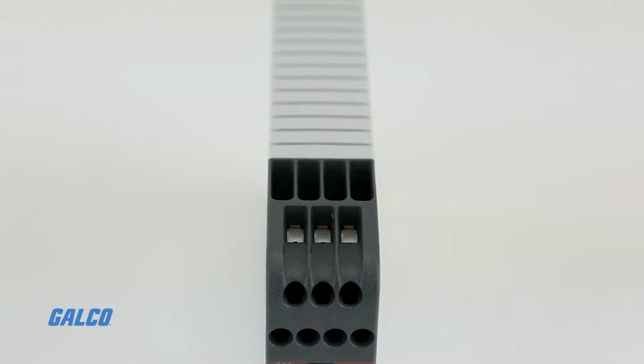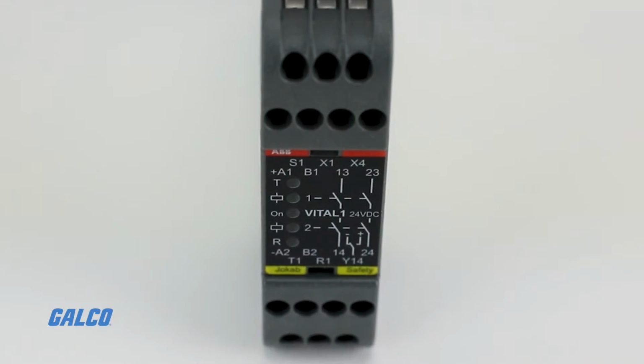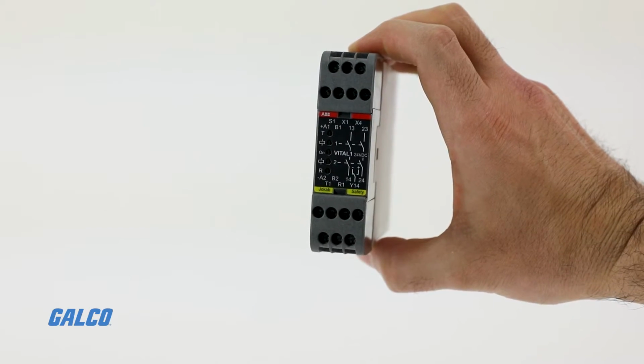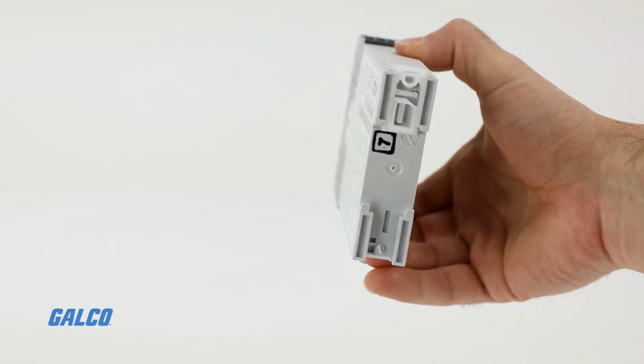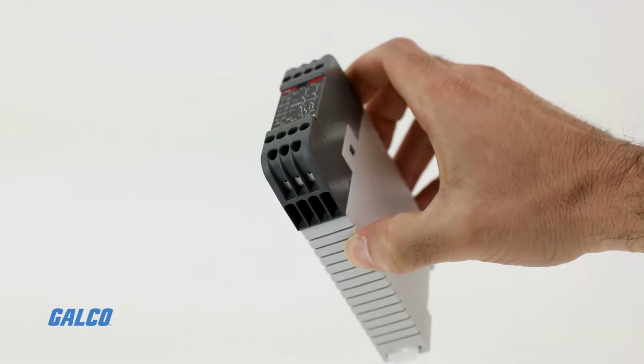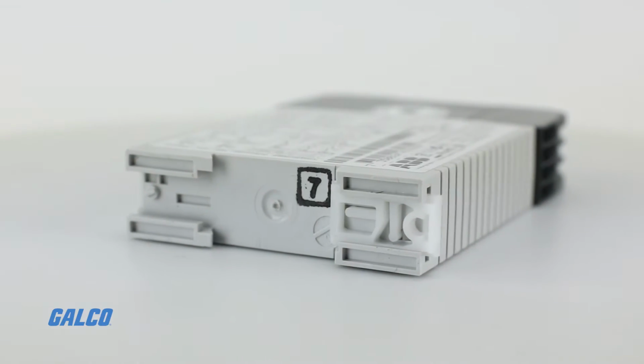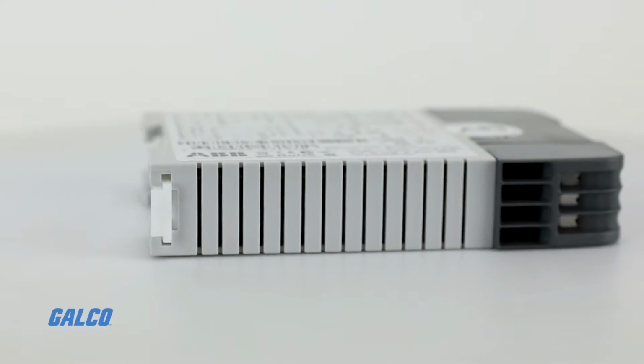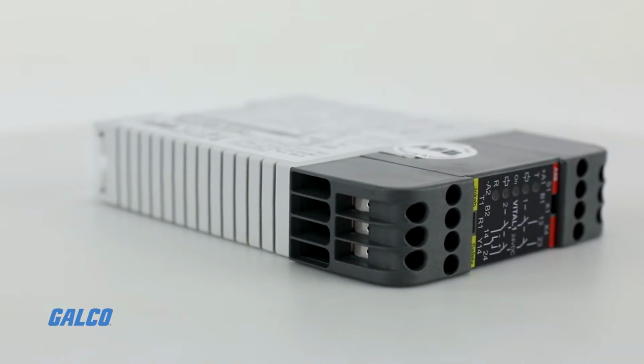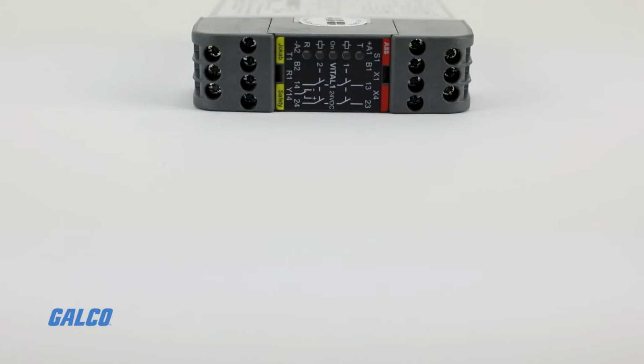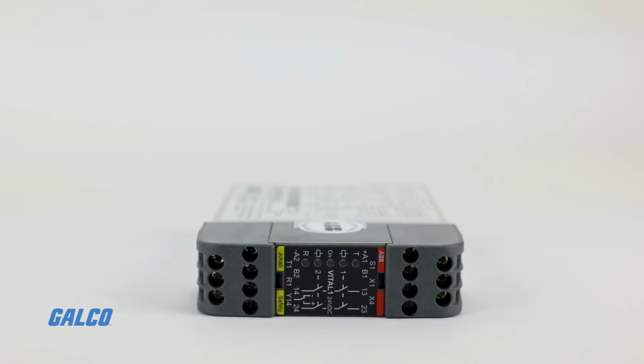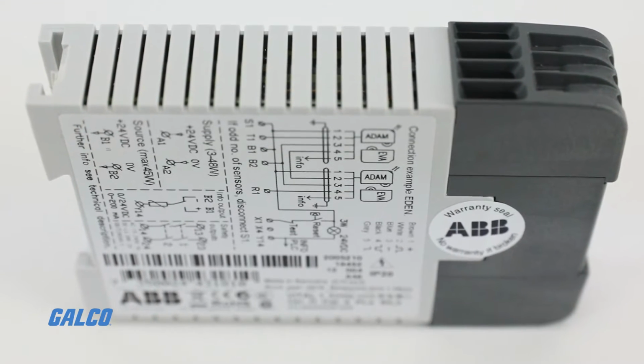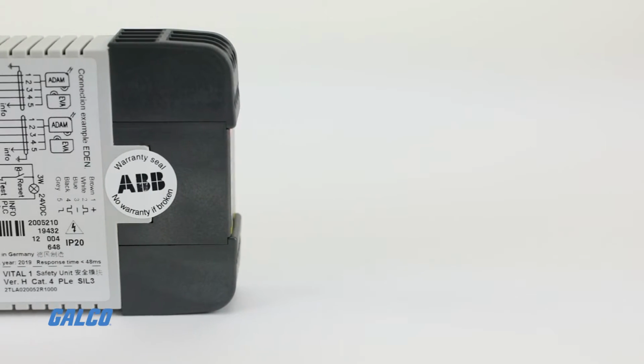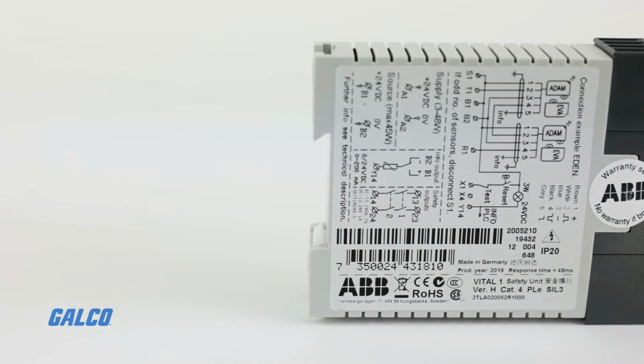With this design, a single safety circuit can accommodate multiple safety components in a series to achieve a redundant safety system. For example, the Vital 1 can monitor both a non-contact safety switch and a safety light beam sensor, so that a process can be interrupted if one component trips when the other does not. When the signal is interrupted, the Vital 1 will deactivate its two built-in safety outputs. Additional outputs are possible with adapter units.